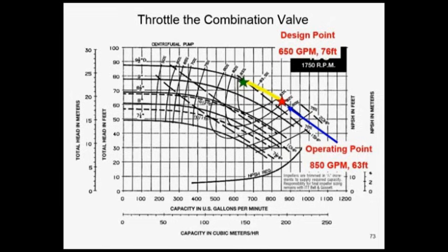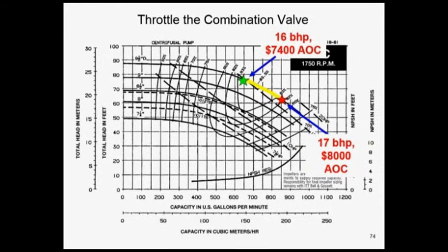Great. Did I save any money? Well, a little bit. It's 6 cents a kW running constantly. I just saved $600 a year. Dropped it from 17 brake horsepower back to 16, and I've got design flow. I'm giving the engineer, I'm giving the owner exactly what they asked for. 76 feet of head, 650 GPM, and I've saved $600. Did I do a good job? No, we did a lousy job.